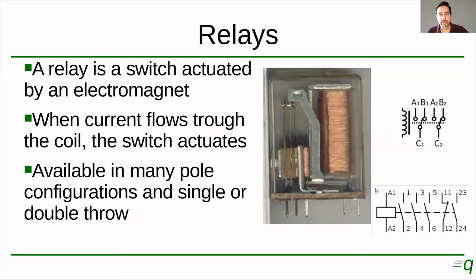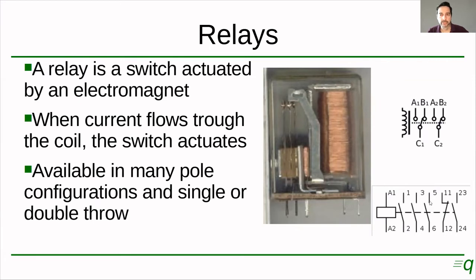This one here is the same idea, only the contacts are different. This symbol you will see more in industrial electronics. This is the coil — A1 and A2 represent the coil. And these are the contacts: 1, 2, and 3 — a single pole, single throw, normally open switch. The switches are drawn in the normal position, meaning when the coil is not energized. So when the coil is energized: one connects to two, three connects to four, five connects to six, and 23 connects to 24.